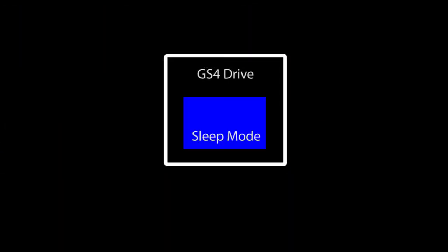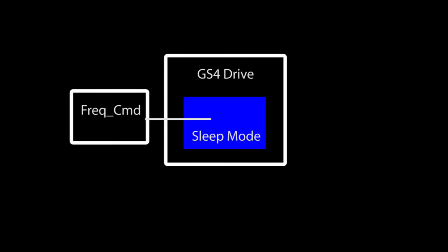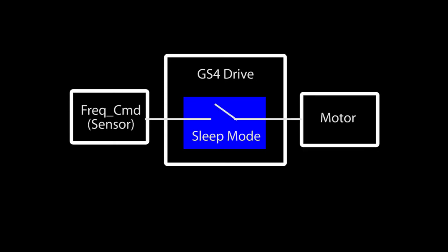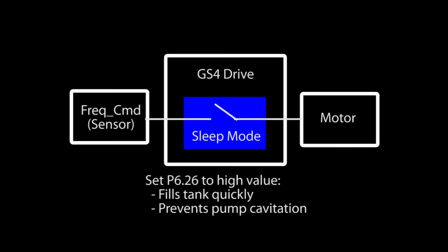The bottom line is, sleep mode watches the frequency command, which in this demo was being driven by the sensor and decides when to let it through to the motor. And we added the trick of adjusting the min drive frequency to a high value and we were good to go.